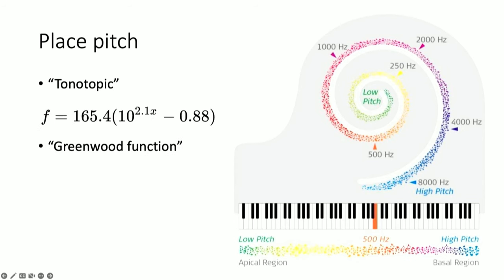The Greenwood function is based on psychophysical research and maps the relationship between pure sinusoidal tones and the position of the hair cells they excite along the length of the cochlea. This function, specific to humans, relates millimeters along the cochlea — the variable X in the equation — to specific characteristic frequencies. It's commonly used as a guide in surgical procedures to ensure the electrode array is inserted deeply enough, because aligning the electrode array so intended frequencies are delivered to correct locations is critical to successful outcomes for cochlear implant users.